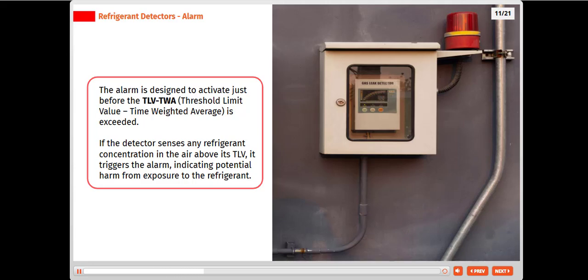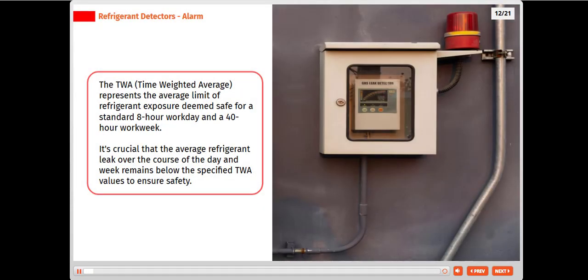If the detector senses any refrigerant concentration in the air above its threshold limit value, it triggers the alarm, indicating potential harm from exposure to the refrigerant. The time-weighted average represents the average limit of refrigerant exposure deemed safe for a standard 8-hour workday and a 40-hour work week. It's crucial that the average refrigerant leak over the course of the day and week remains below the specified TWA values to ensure safety.